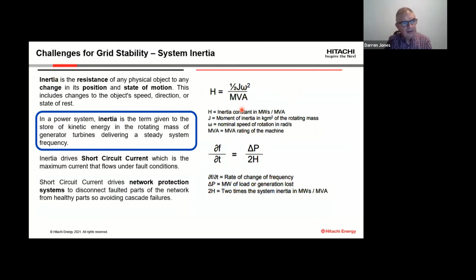What we can see, we have here the equations that describe inertia and the inertia constant. I mean, in some ways, inertia constant is just a mathematical concept. It doesn't actually exist in real life. It's just a mathematical concept that's used by network designers for them to be able to design networks successfully. And again, most people, I guess, will recognize this equation on the top. It's just half the mass times the velocity squared, in its rotational form. So it's just simply the inertia constant is just simply the store of kinetic energy divided by the system power, and that inertia is used as a fundamental design parameter when people are designing new networks to make sure that they remain stable.